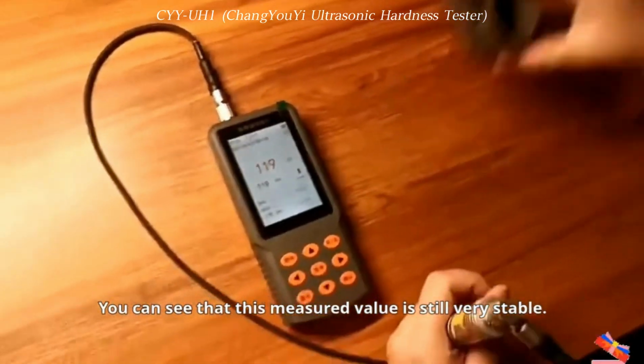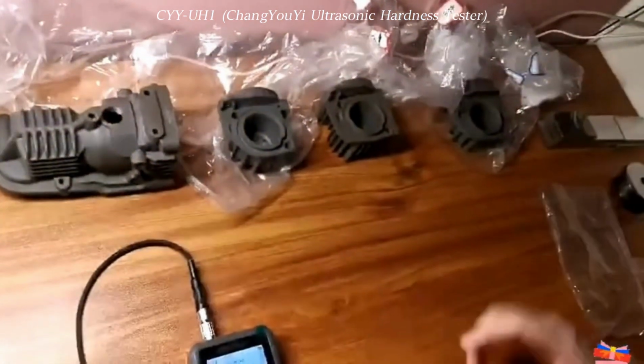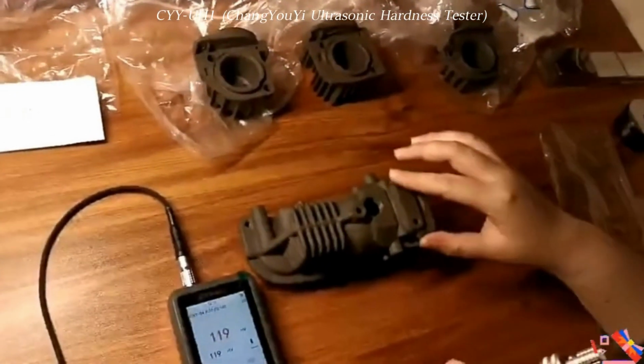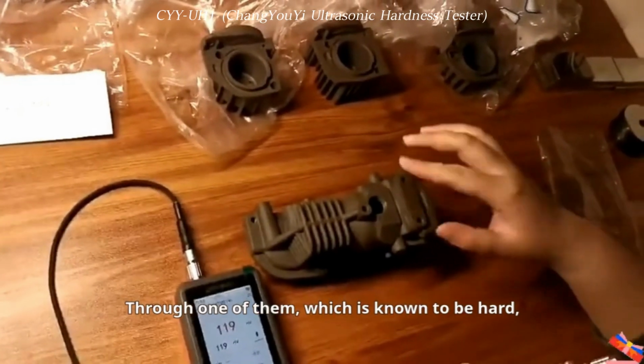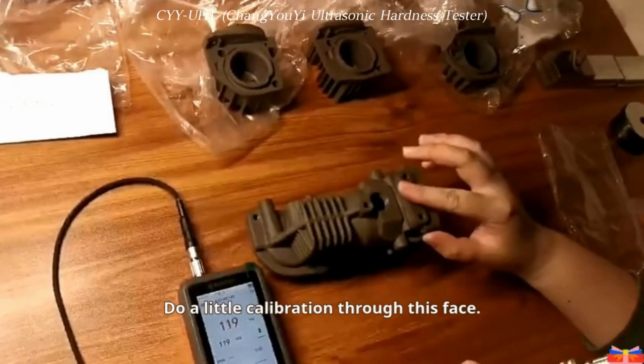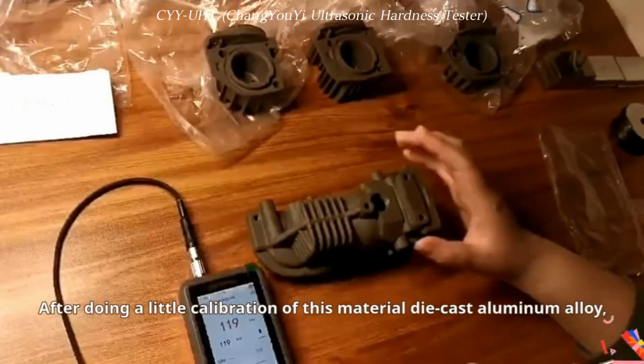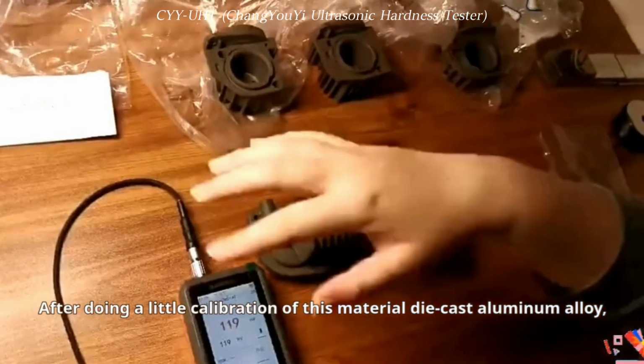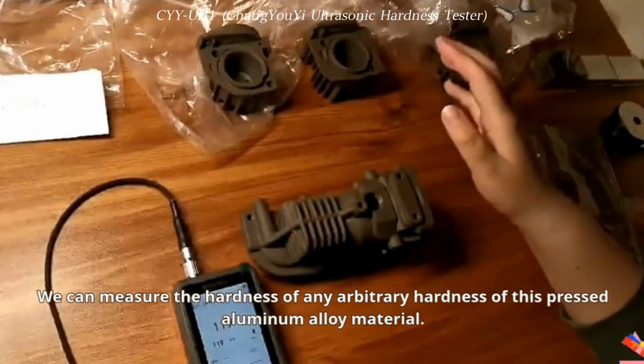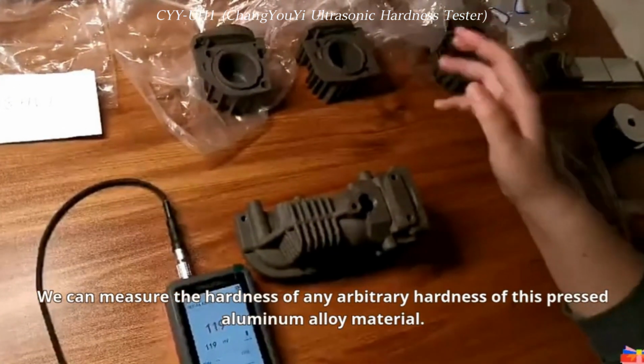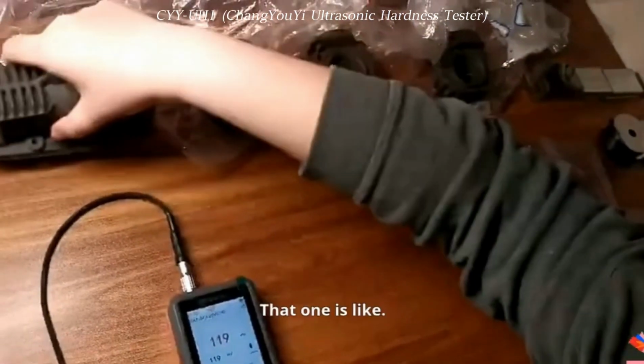You can see that this measured value is still very stable. Well, in this way, we do a single-point calibration on one of them, which is known to be hard, through this face. After doing a single-point calibration on this die-cast aluminum alloy material, we can measure the hardness anywhere on this die-cast aluminum alloy material.